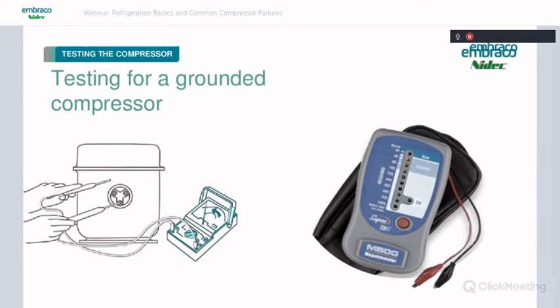And it's a very simple operation. Just connect one lead to the terminal and one lead to an unpainted surface of the compressor body. Hit the button and look at the LEDs. It's going to give you red, yellow, green, yellow, or red at a certain, below a certain megohm reading.